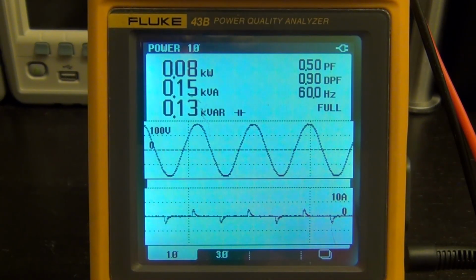We have 0 phase offset between the current and the voltage, so the cosine of that is going to be 1, and it's going to have no problem. But there's a little bit of leading here, and that's why the displacement power factor is not 1. But the total power factor is only 0.5, and that's because the total harmonic distortion is taken into account, and that is going to reduce our total power factor significantly. And this instrument can show us that total harmonic distortion problem. I just have to go to the next screen.